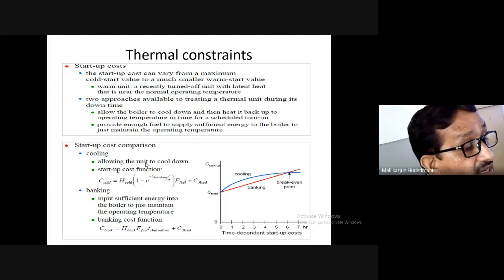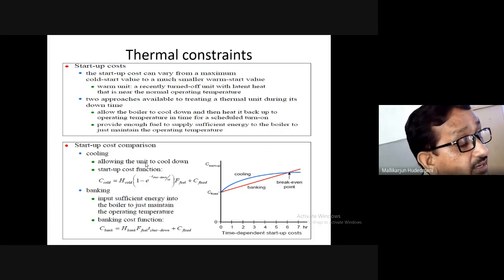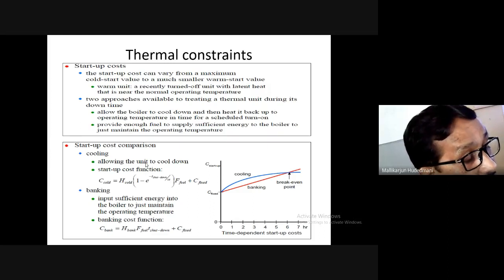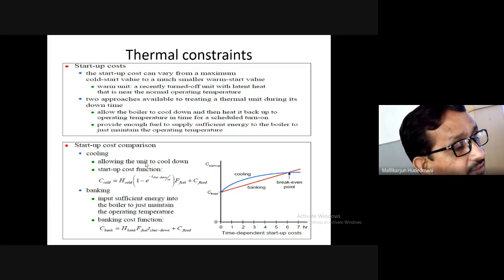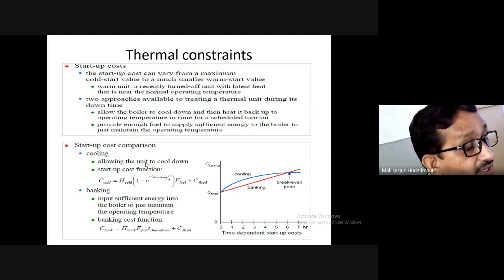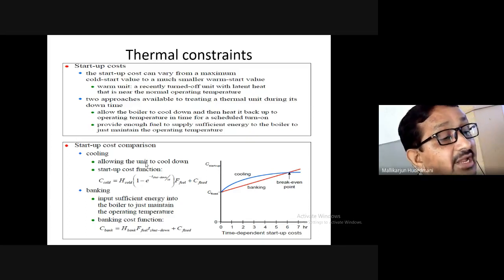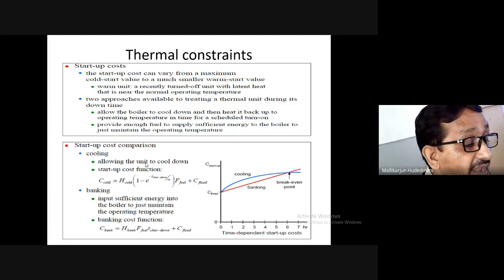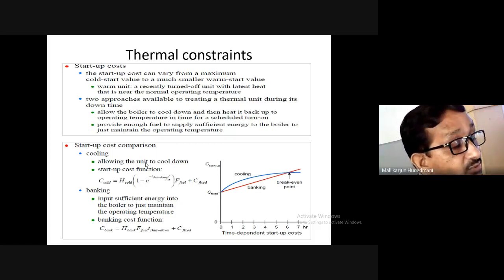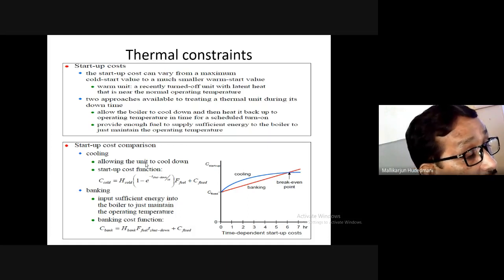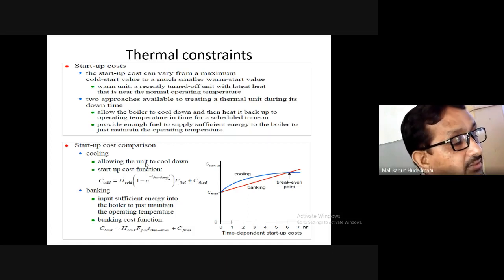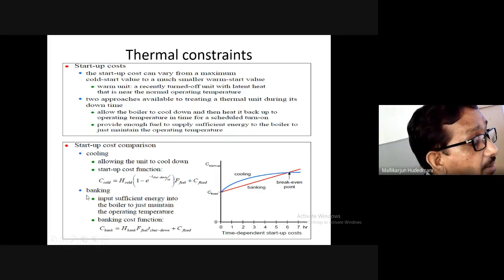Banking is the process of maintaining a decommitted unit at a lesser temperature than the working temperature, burning minimum fuel, which on requirement can be brought online immediately by increasing the fuel conditions. The cost of bringing a banked unit online is lesser than bringing a machine from room temperature to online, both in terms of investment and hours required. That is how cooling and banking are compared.